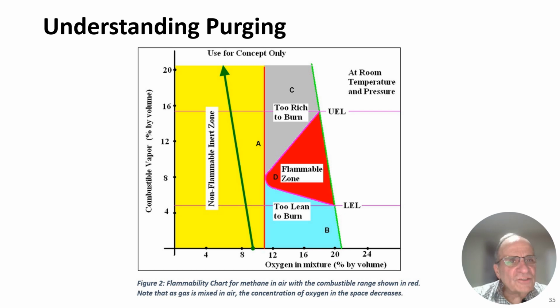I've already mentioned purging, and I'll go over that again just on this slide to emphasize the fact that once you get the content of the vessel below a certain concentration, and I go in accordance with the AGA guidelines, then you can introduce gas into that vessel without the concern of reaching the flammability zone. Now, keep in mind, this is temperature dependent.